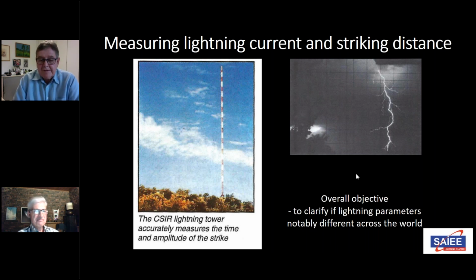We learned from this that the ropes the post office told us to use turned out to be fiberglass rods, which delaminated during the high wind vibrations. With rain entering those cracks, and then lightning striking the tower, we got discharge into the rods and they fractured, so the tower fell. We had to solve the problem by finding suitable insulating ropes that wouldn't be affected the same way. As engineers, we learned a lot of practical problem solving along the way.